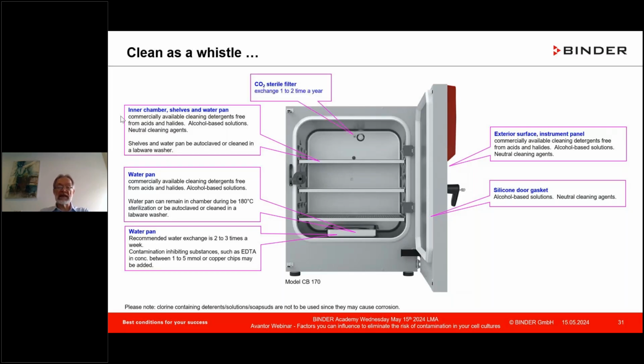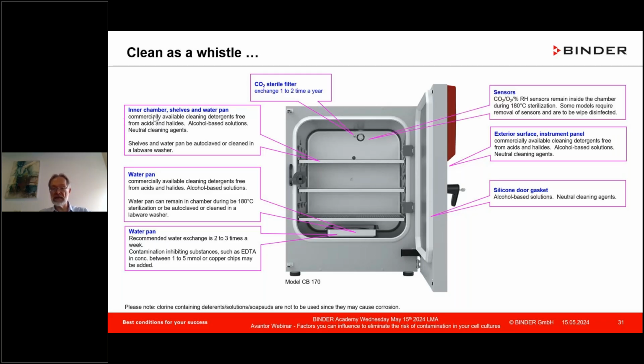Sterile filter, and get this correctly, ladies and gentlemen, I'm not talking about the HEPA filter inside as with Model A. I'm talking about a HEPA filter, a particle filter, for the gas coming from the gas bottles. Before it enters the CO2 incubator, the particles coming from that gas bottles are caught by a syringe filter type little filter. All right, and that also has to be exchanged 1 to 2 times a year to ensure a good CO2 supply.